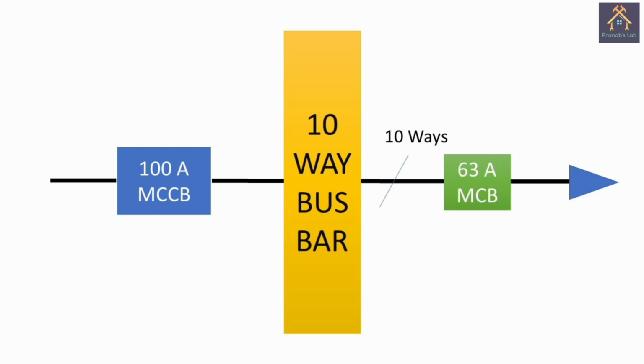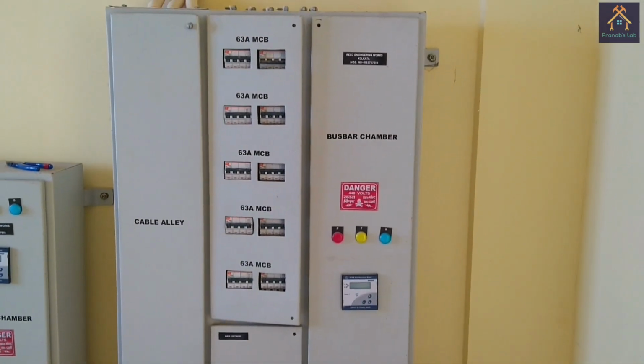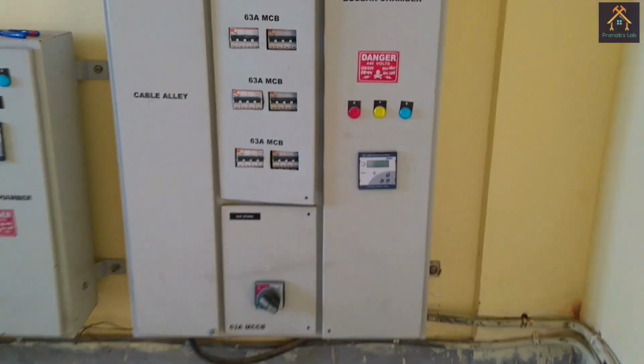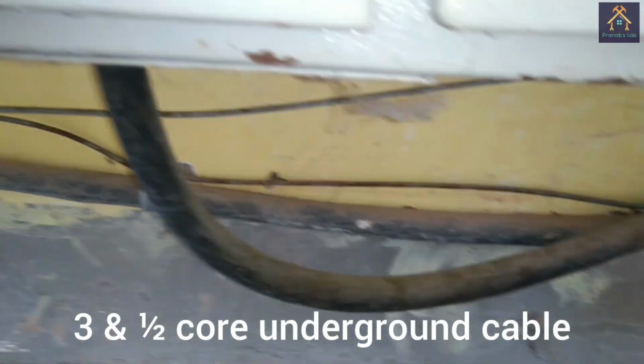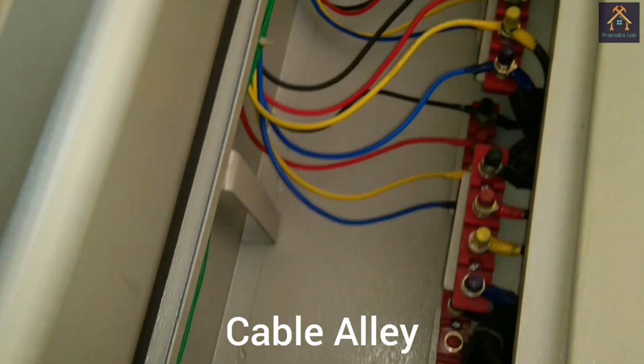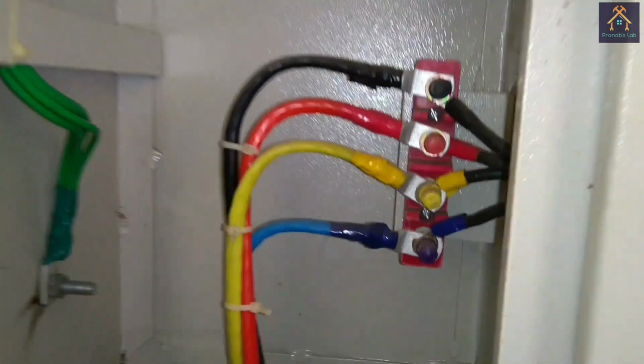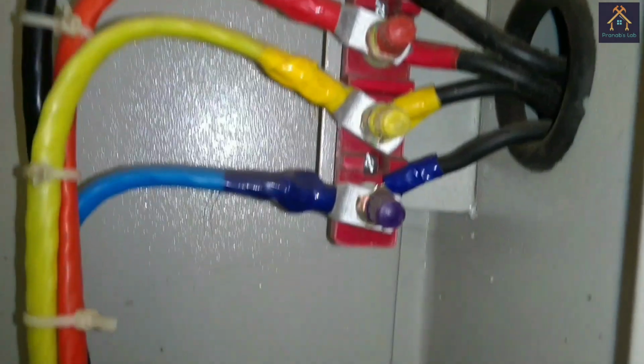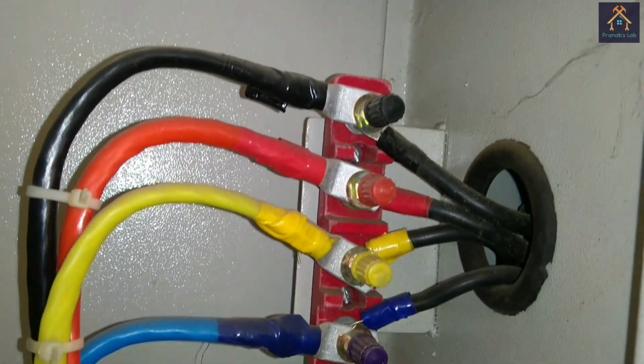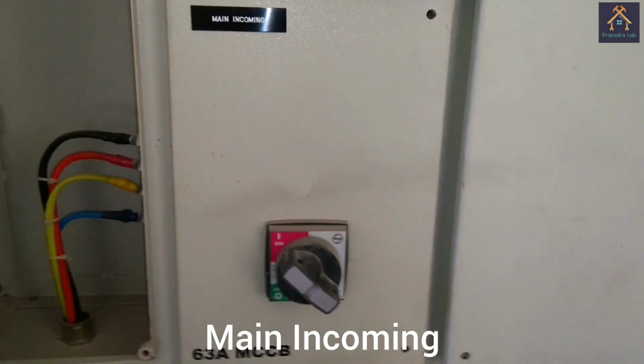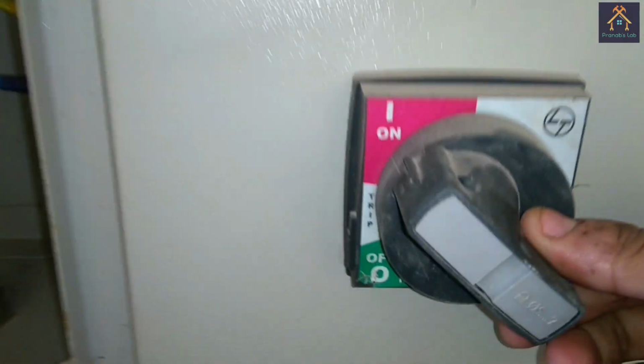Now let's see the panel practically. You can see the different chambers of the panel. The 2 cables are coming out from the underground, and one of them is inserted into the Cable Alley chamber, and the 4 different colored cables, that is red, yellow, blue phase and neutral black, are connected with 4 different terminals. The connected cables are inserted into another chamber named the main incoming 63 ampere MCCB, that means molded case circuit breaker.